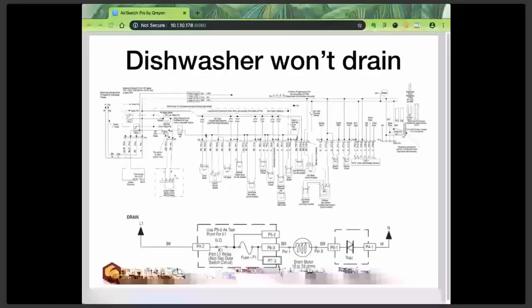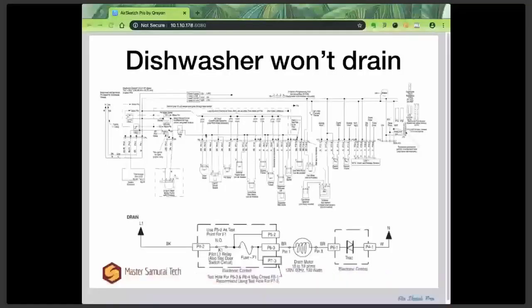Hope you're all saying drain pump, right? Now, do we need to lay on the floor like a monkey and remove the kick panel and fumble around with our meter and try to back probe the drain pump and see if it's getting power or voltage, actually, more precisely? Personally, I hate laying on floors, and if I can avoid that, I will. I'll do it for part replacement, whatever.